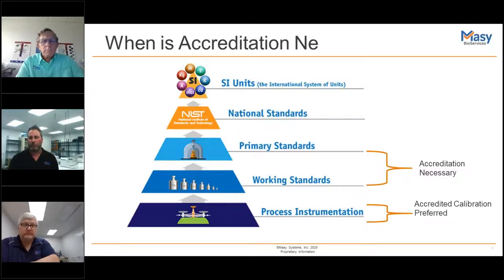For process instrumentation, accredited calibration is preferred. The reason we say preferred is take a system, an RO system or a WFI system or anything like that. If it has a pressure gauge on it, and that gauge's functionality is reference or non-critical, just for a facilities technician or process engineer to walk by and visually confirm that pressure or liquid is flowing through the pipe, it is not the critical measurement for the device.